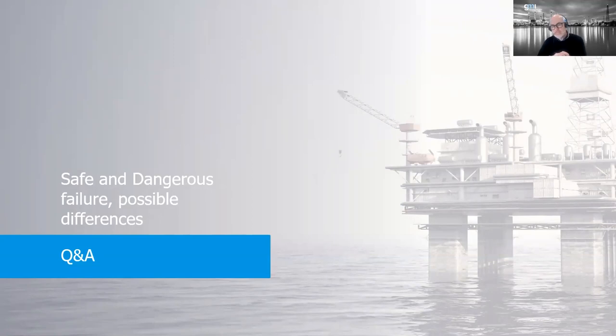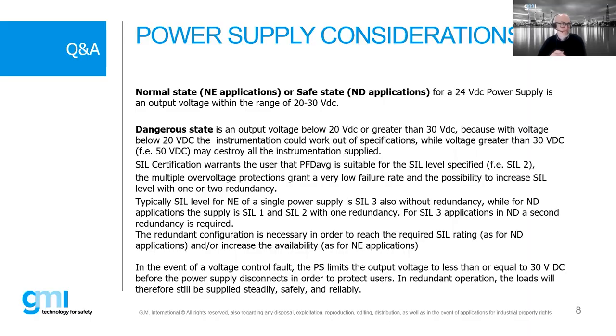Okay, Andrea. To understand the importance of using a safety power supply system, it is important to understand the difference between safe and dangerous failure. What is the difference between them? Okay, so say the normal status is between 20 and 30. Dangerous failures are below 20 and higher than 30, as we already repeated a lot of times. So below 20 the instrumentation works out of specification, while at more than 30 you can destroy the connected instrumentation.